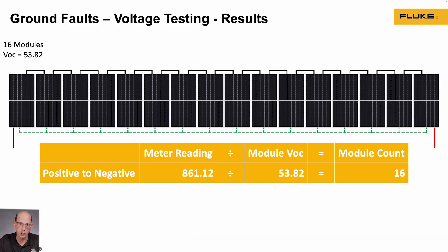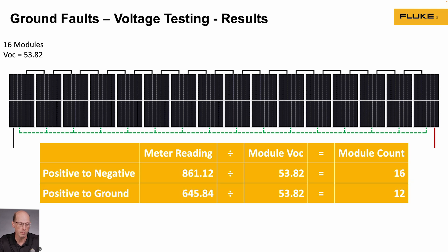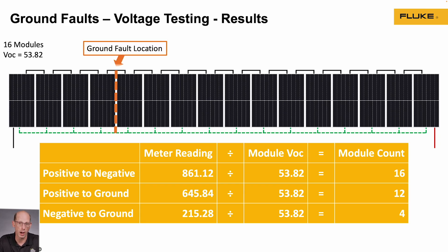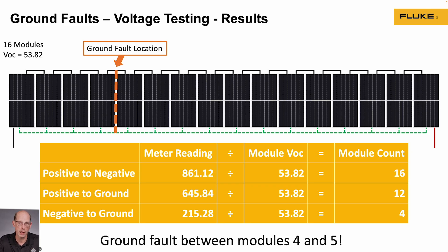When I look at the voltage readings: positive to negative was approximately 861 volts — divide that by 53 volts per module and I get about 16 modules, which is what I'd expect. Positive to ground of 645 volts divided by 53 volts gives me about 12 modules. Negative to ground of 215 volts divided by 53 gives me about 4 modules. This tells me there are 4 modules between the negative and the ground fault, and 12 modules between the positive side and the ground fault — meaning the ground fault is somewhere between module 4 and 5.